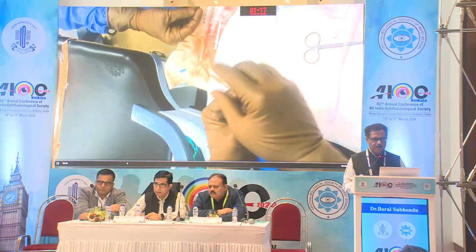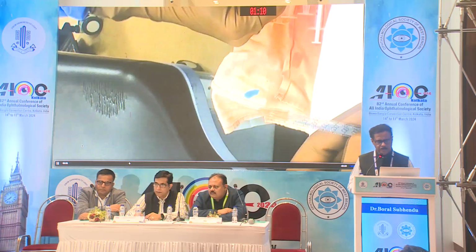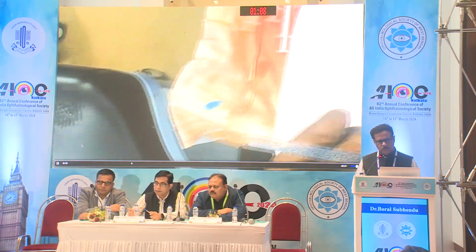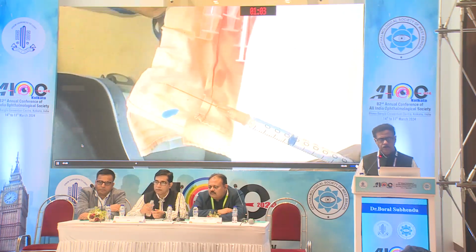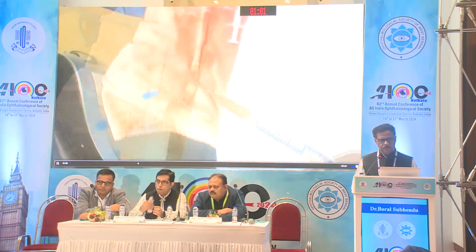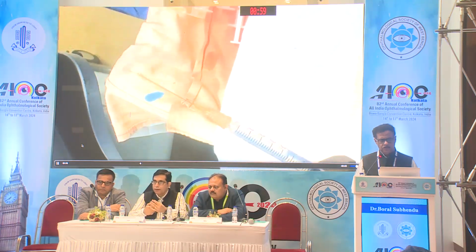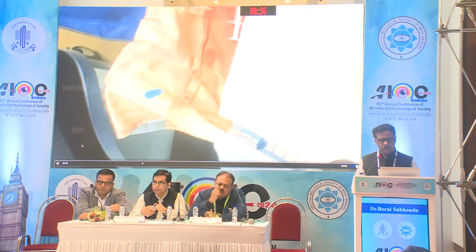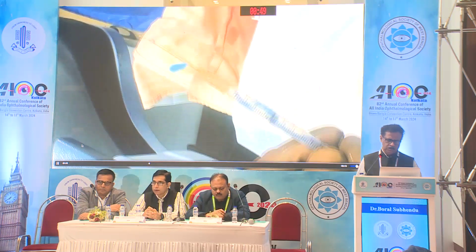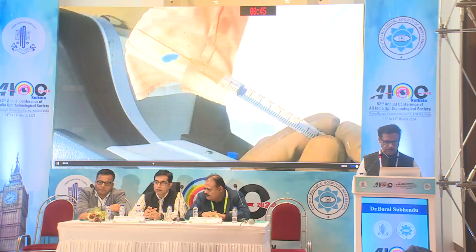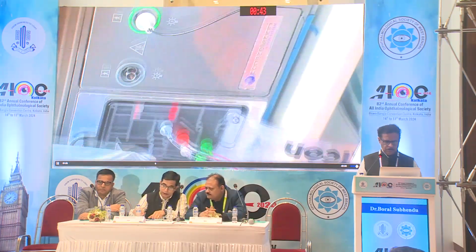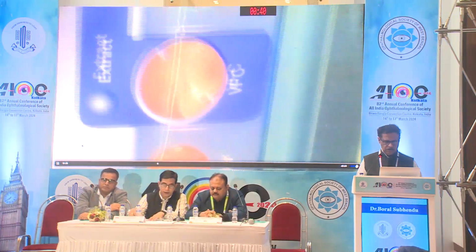Attaching either a 38 gauge or 41 gauge subretinal needle to the syringe, we can extract retained submacular PFCL bubbles or deliver a precise dose of subretinal drugs like RTPA for subretinal hematoma in a controlled way. Here the cut rubber tip of the plunger can move smoothly within the 1 ml syringe during injection or extraction mode of the VFC attached with the vitrectomy machine. We named it Micro VFC.